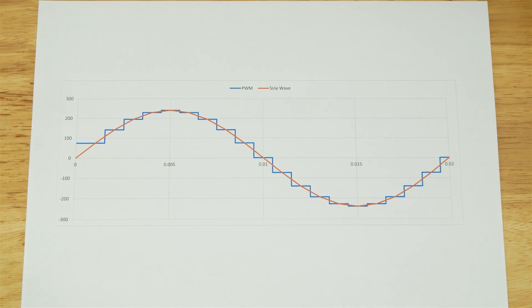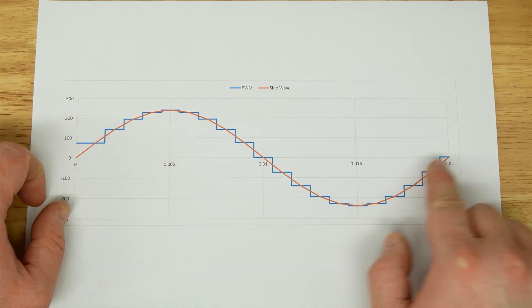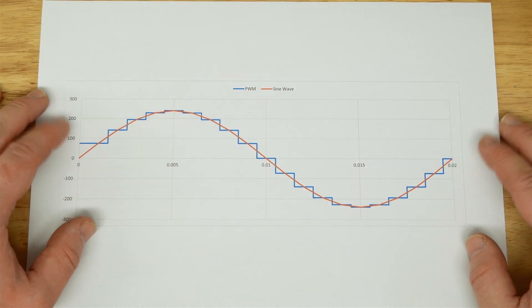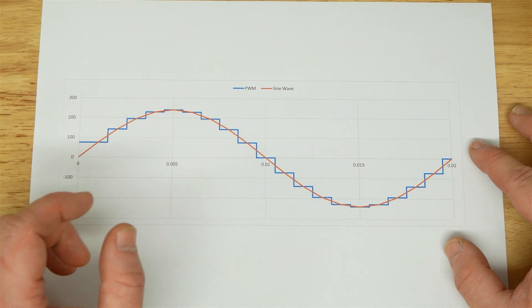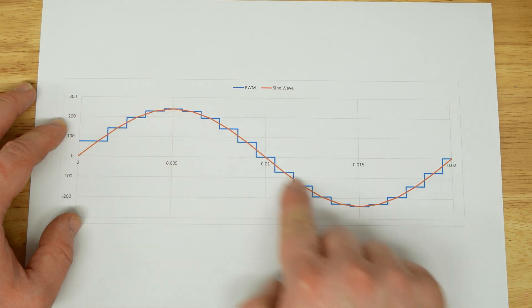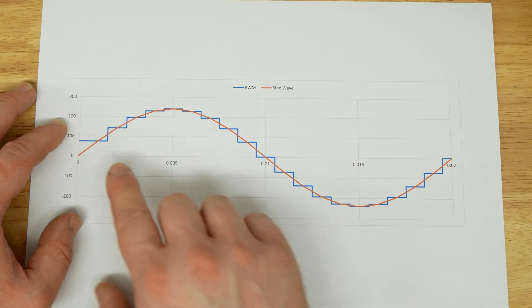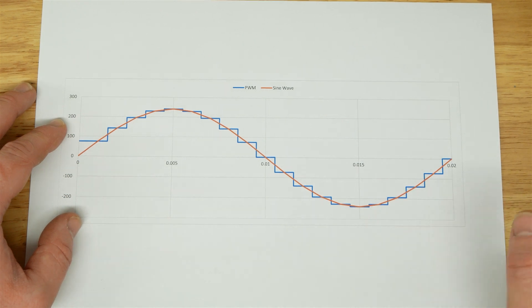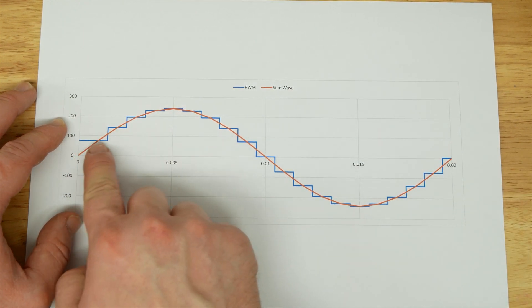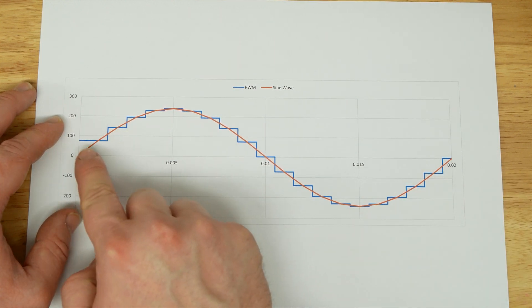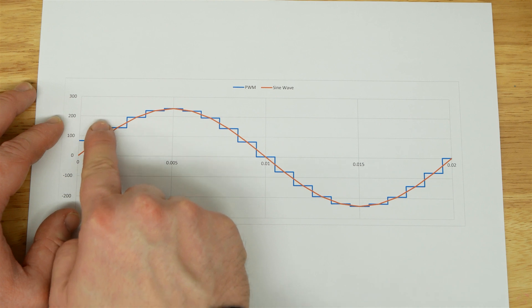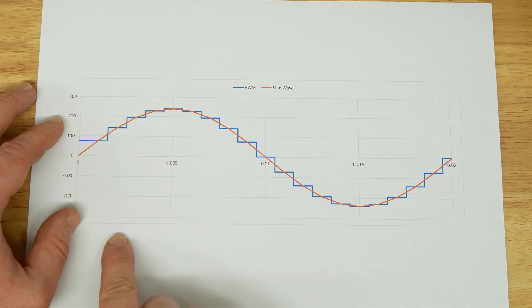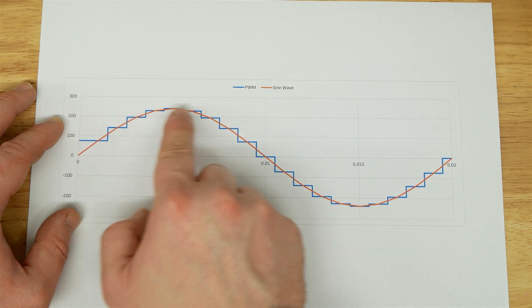This is a crude representation of what the VFD actually does. Instead of producing a sine wave output, which is our orange line here, it actually produces a square wave. It's pulse width modulated, which means it varies the frequency of the voltage output to approximate the waveform. The steps here should be different widths because that's the frequency. Ideally you'd see this come along, drop down to zero, have a short gap and come back up, gradually getting longer.